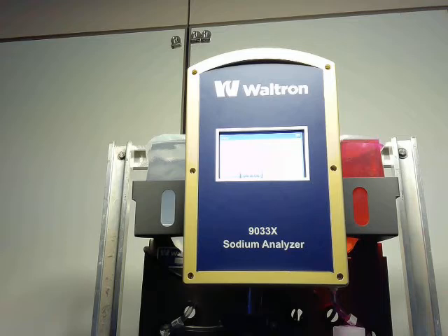If the analyzer passes calibration, especially the auto cal, if you have it set for midnight on a Tuesday, it'll kick onto its auto cal, go through its calibration, and go back online. If it passes, you probably won't even notice that it went through its calibration. It'll be back online and keep going. If it fails, it'll go back online, but it will give you that failure message just to let you know, hey, something's not totally right.